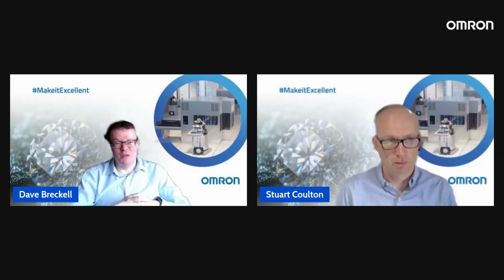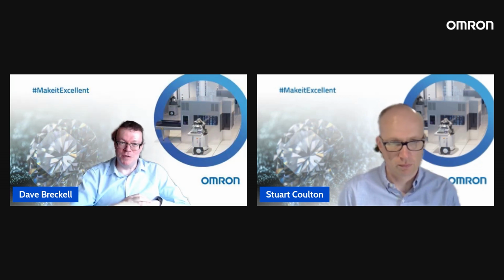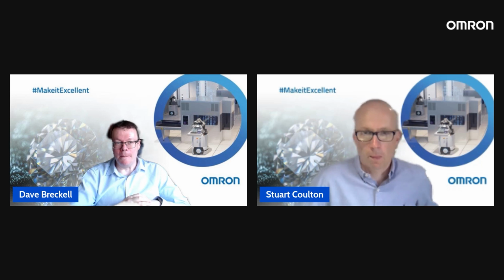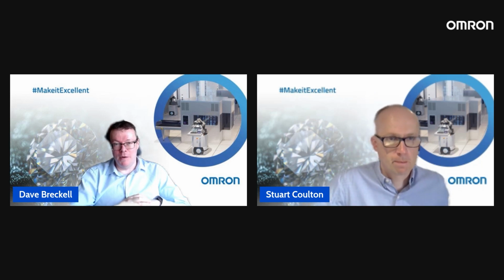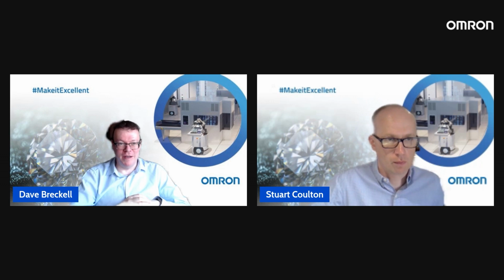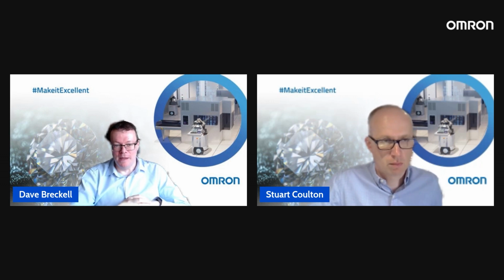Some things, especially when you start talking about specialist motors and other things, can be on quite a long lead time. Some of our machine builders will actually use that data as well to provide a spares package, so they can organise for a maintenance engineer to be available at a certain time. And it also lets you balance your machines and line use. So if you've got 3 lines and one of them has been used an awful lot and there's a bit of degradation on the motors, you can balance the load across the other 2 to keep them running longer until you hit that maintenance window.